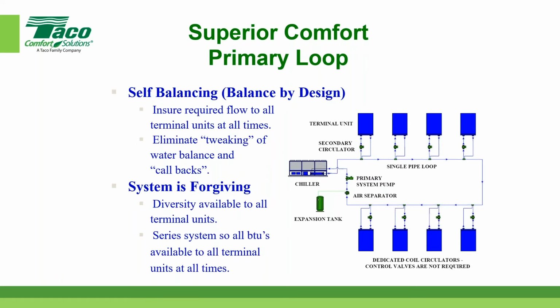You have anything to add into any of that, Rich? Nope, but there's a question for another individual. It says, won't the farthest zones from the chiller source suffer under the full load? And I think he's talking about the cascade, which you're going to get into in a few minutes. Yeah, I'll get into that. And the answer is, as long as you consider the design and there's the proper delta T and you have enough flow in here, and this one's designed accordingly, that temperature entering that one there would still be sufficient. So I'll talk about that a little more when we get into the cascading. So give me a minute or two on that one, please.